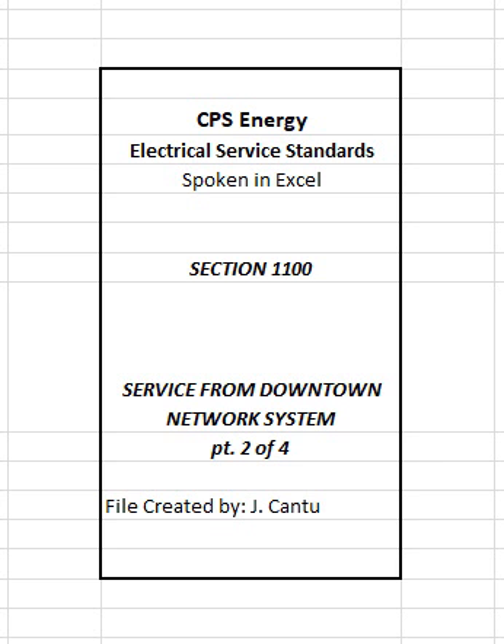2. Entrance doors shall be equipped with locks, and fire doors shall be kept locked with access being allowed only to CPS Energy personnel. Locks and latches shall be arranged so that the door can be readily and quickly opened from the inside by a panic bar, pressure plate, or other devices that are normally latched but open under simple pressure, per NEC. The second door must be fitted with surface bolts inside at top and bottom.